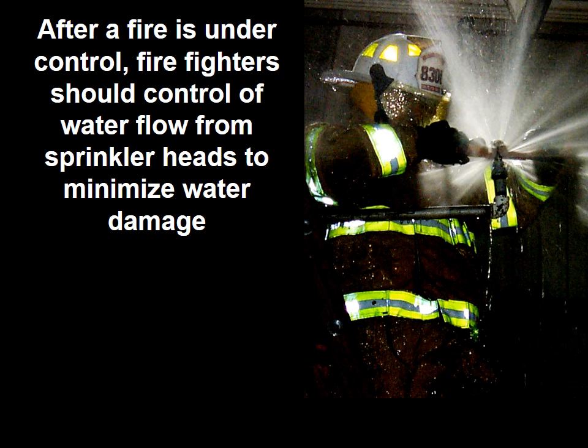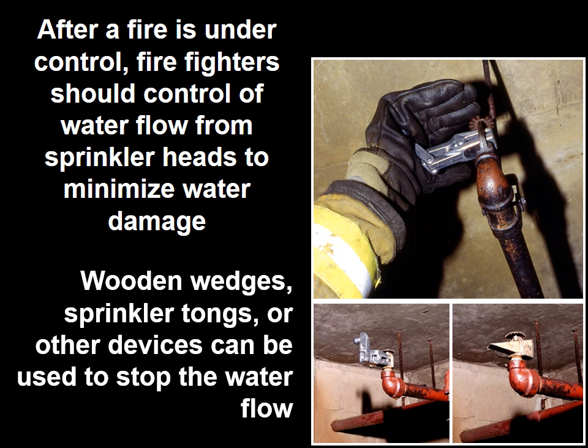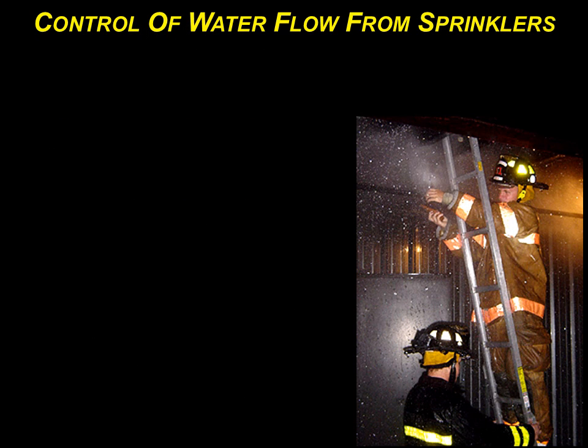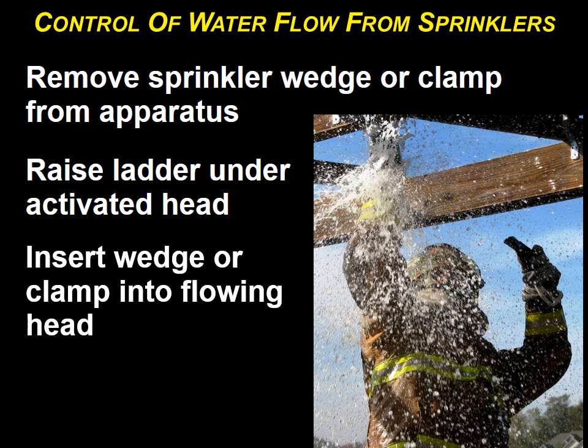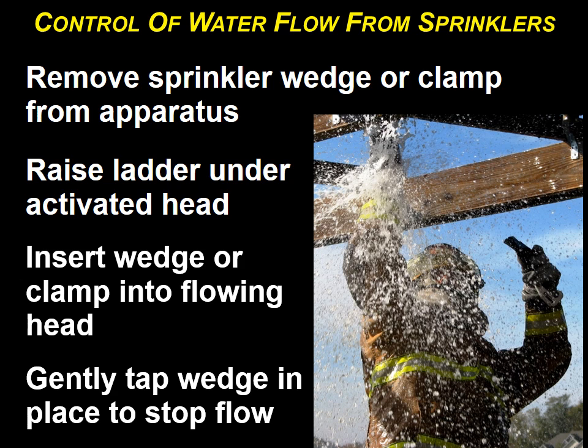After a fire is under control, firefighters should control the water flow from the sprinkler heads to minimize water damage. Wooden wedges, sprinkler tongs, or other devices can be used to stop the water flow. Remove the sprinkler wedge or clamp from the apparatus, raise a ladder under the activated head, insert the wedge or clamp onto the flowing head, and gently tap the wedge into place to stop the flow. You may have to use 2 wedges, one from each side, in order to completely stop the flow. It just depends on the sprinkler head itself.